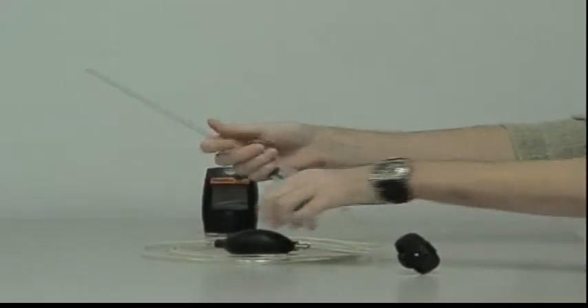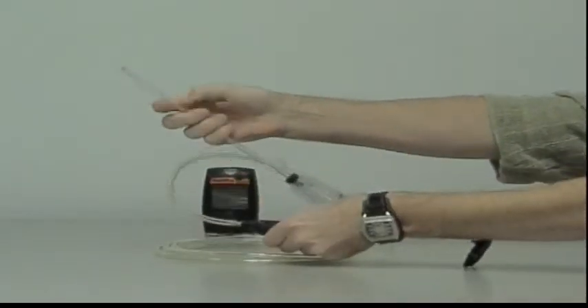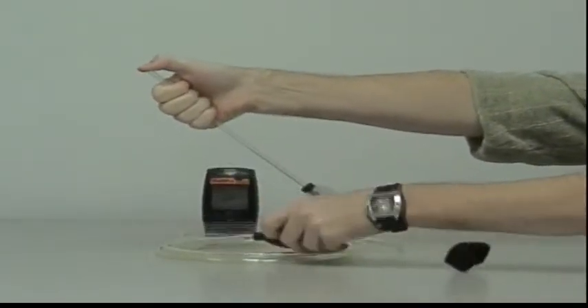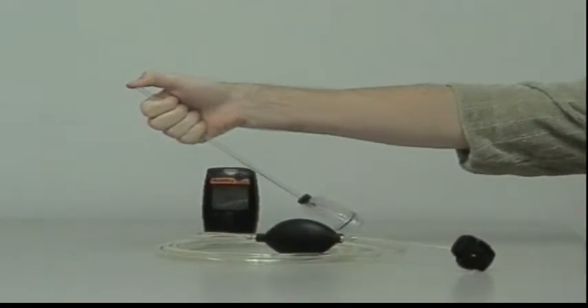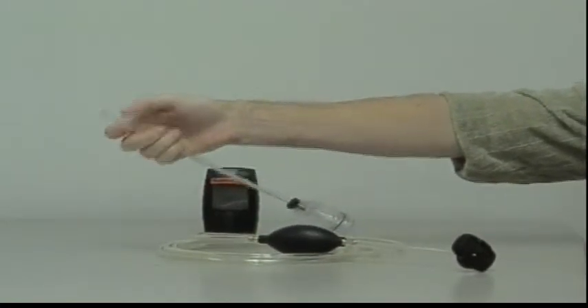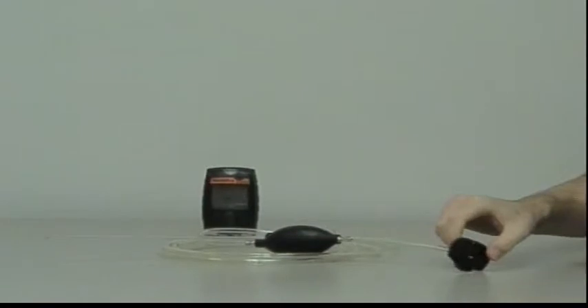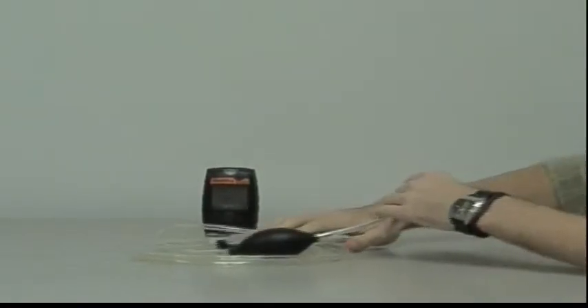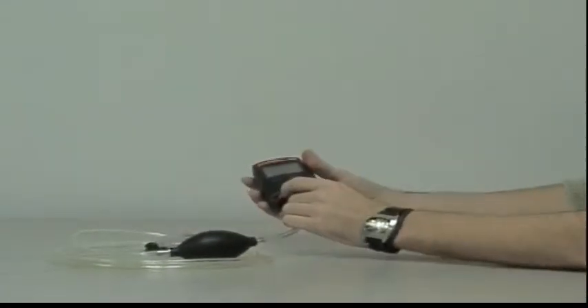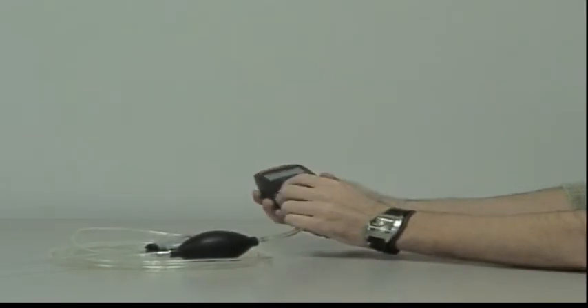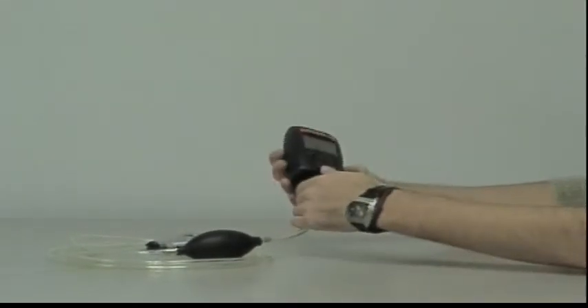Before using the manual sample draw kit, the seals must be tested to ensure they are adequate. To test the seals in the sample draw system, cover the end of the sample draw probe with a finger and squeeze the aspirator bulb. If there are no leaks in the sample draw kit components, the bulb should stay deflated for a few seconds.